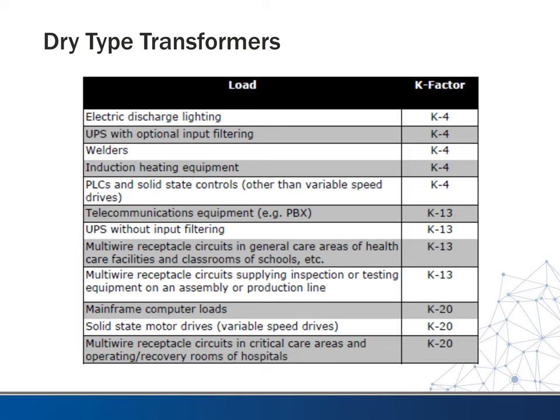So here's a table that gives you an idea and some guidance as to what you might want to specify. If you have electric discharge lighting, like HID lighting, we'll talk about that later, you might want K4. UPS with optional input filtering, K4. If you have a welder, induction heating, PLCs and solid state controls, K4. Now, if you move up to telecommunication equipment, so if you have a telecom room with a transformer, you're probably going to want that to be K13. UPS without filtering, multi-wire receptacle circuits and general care areas of healthcare, because a lot of the healthcare equipment is digital now, it's computerized, K13.